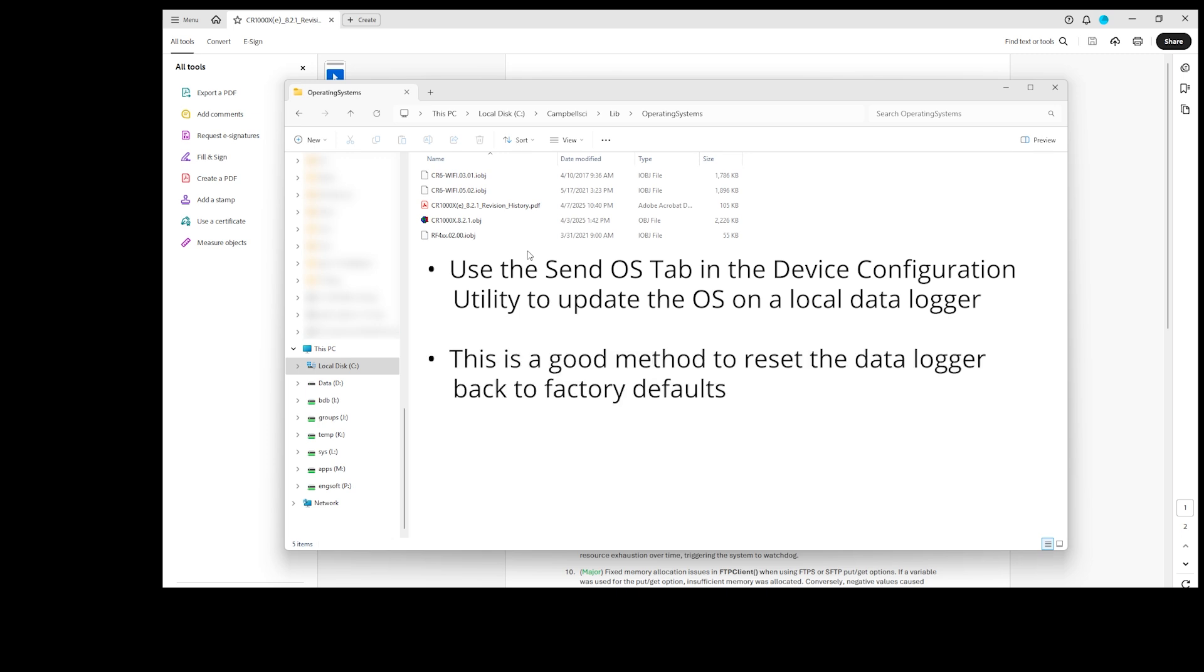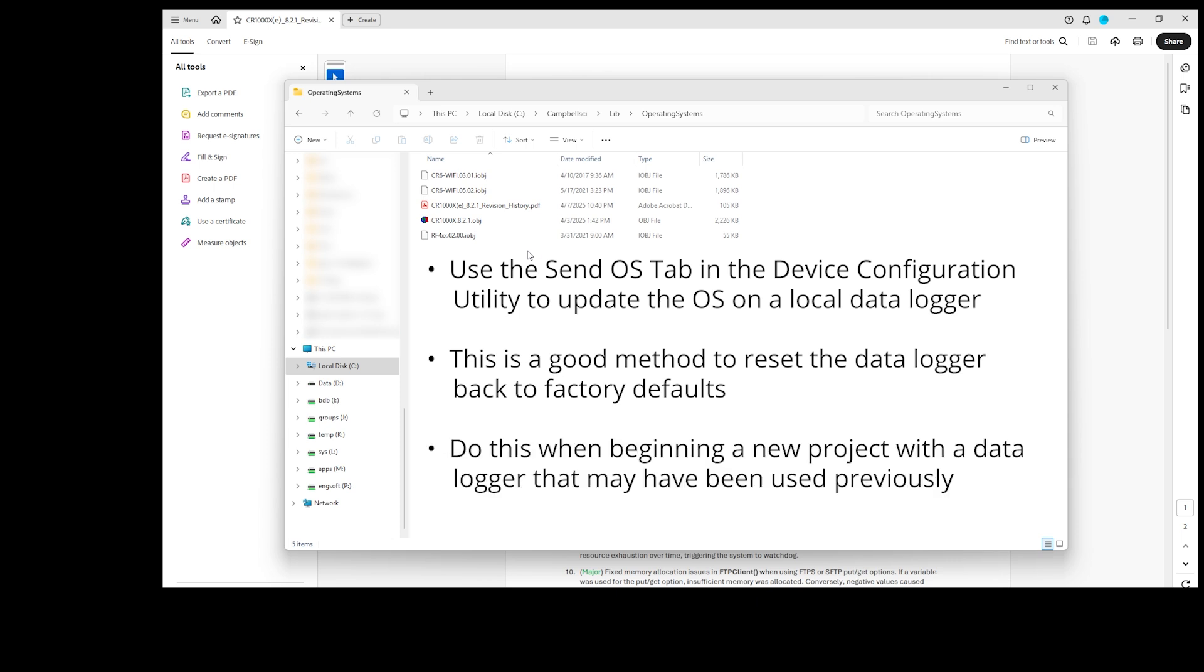In this video, I'll use the Send OS tab in the Device Configuration Utility to update the OS on a local data logger. This is a good method to reset the data logger back to factory defaults. I always do this when I begin a new project with a data logger that may have been used previously. For this method, I need to connect my computer to the data logger directly, not over a telecommunications link.